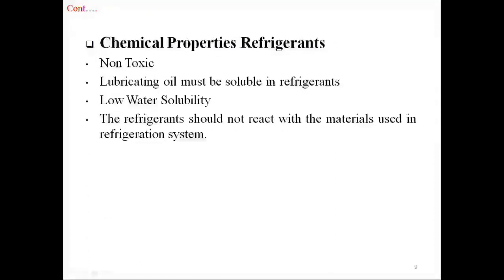Chemical properties of refrigerants. Refrigerant should be non-toxic. Refrigerant used should be soluble in lubricating oil. If the oil is not miscible in the refrigerant and it is heavier, it will settle down in the evaporator and reduce heat transfer; therefore oil separators are to be employed. Refrigerants should have low solubility in water, otherwise most refrigerants form acids or bases in the presence of water, causing corrosion and deterioration of walls, seals, and metallic parts. The refrigerants should not react with materials used in the system such as evaporator, condenser tubes, compressor, and control valves.